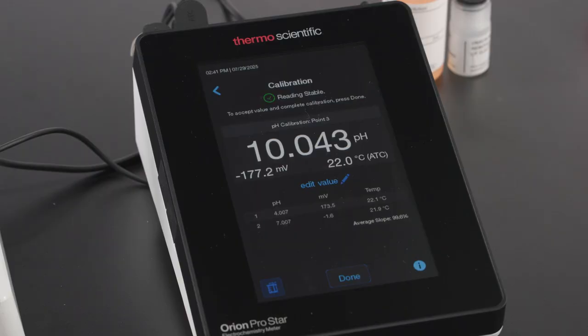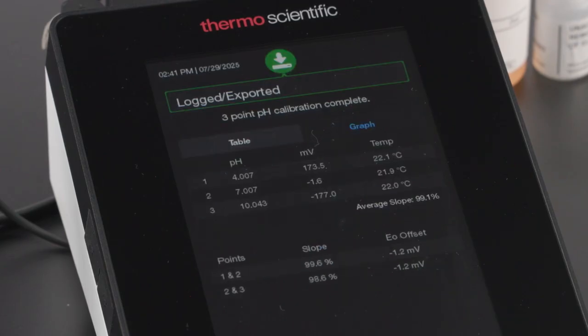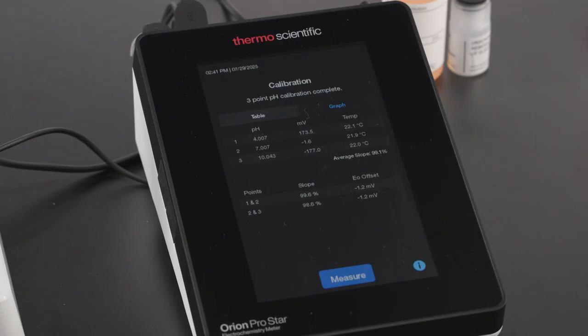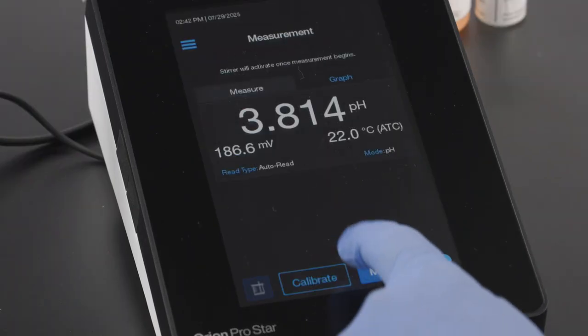You can accept the results of the third calibration point and complete the calibration by tapping the Done button. The calibration summary shows all 3 calibration points, the average slope, and the segment slopes. An average slope of 92 to 102% is generally acceptable. Check the segment slopes. When they are both similar, it indicates that all 3 buffers have retained their integrity and have not degraded. You can be confident that the electrode is working, the calibration buffers are valid, and that the calibration is good. Tap the Measure button to view the measurement menu.